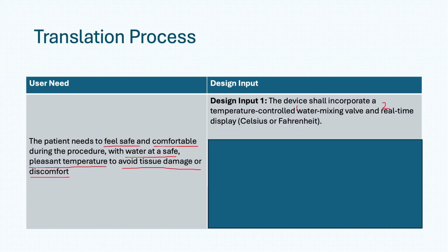As we translate that user need into design inputs, the first design input could be something like this one. The device shall incorporate a temperature-controlled water mixing valve with real-time digital display. Now here are two things together, the mixing valve and the display. They may work together, or you can have two separate design inputs right there. The bottom line, there has to be some type of control as needed by the user need or from the user.